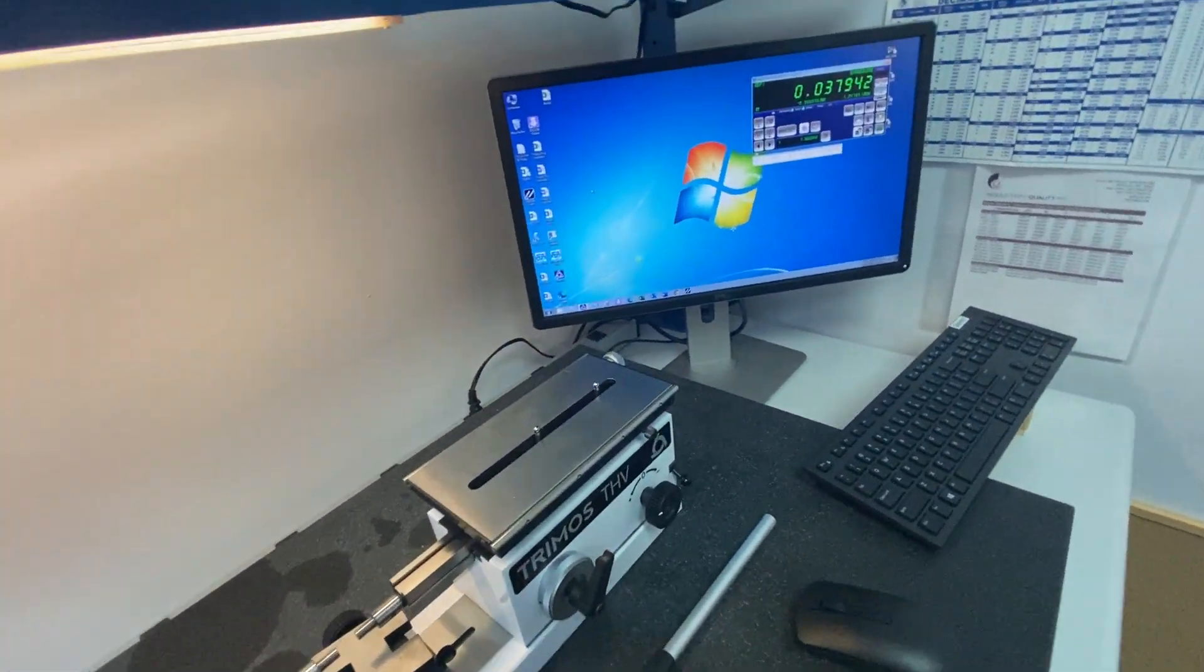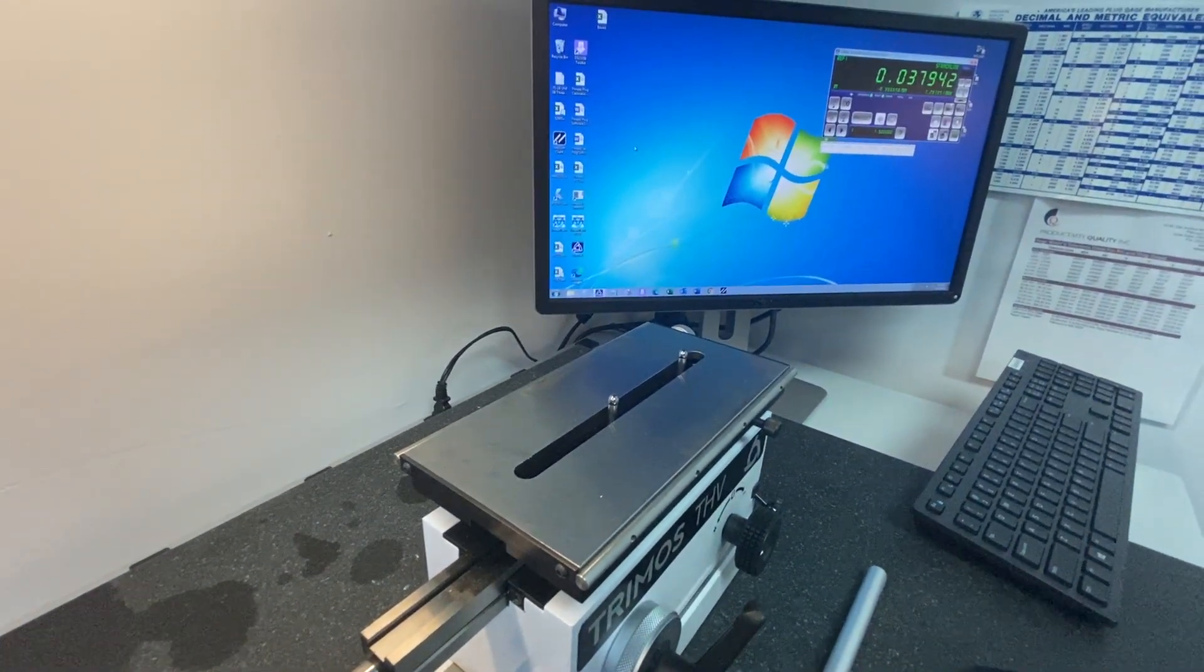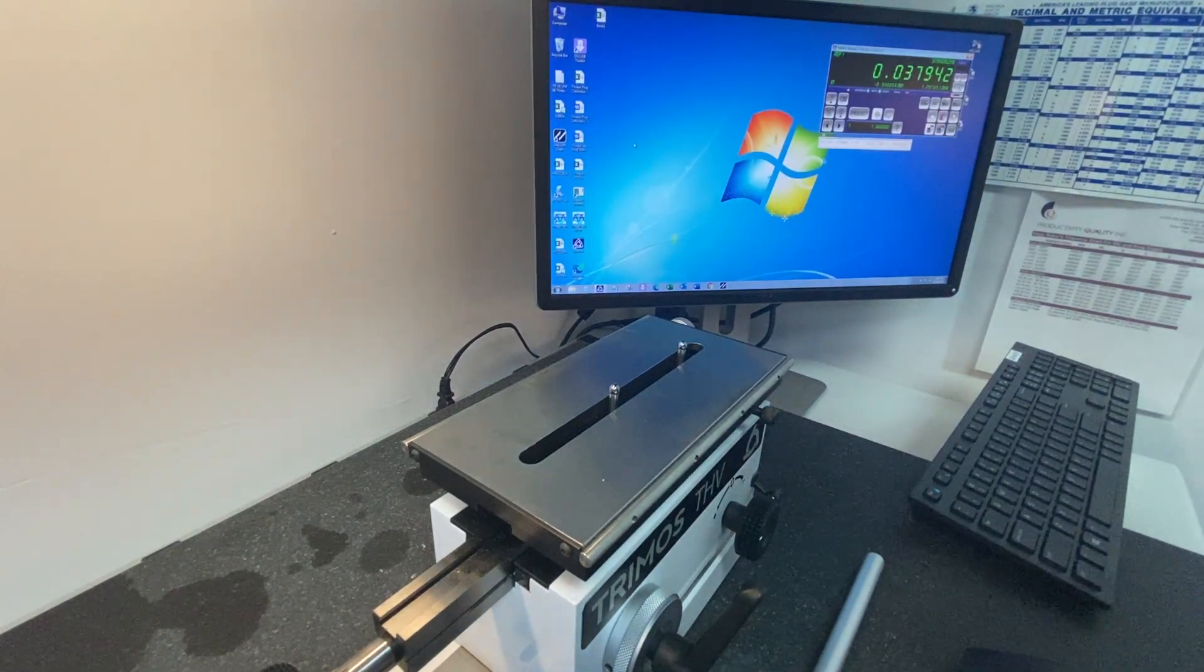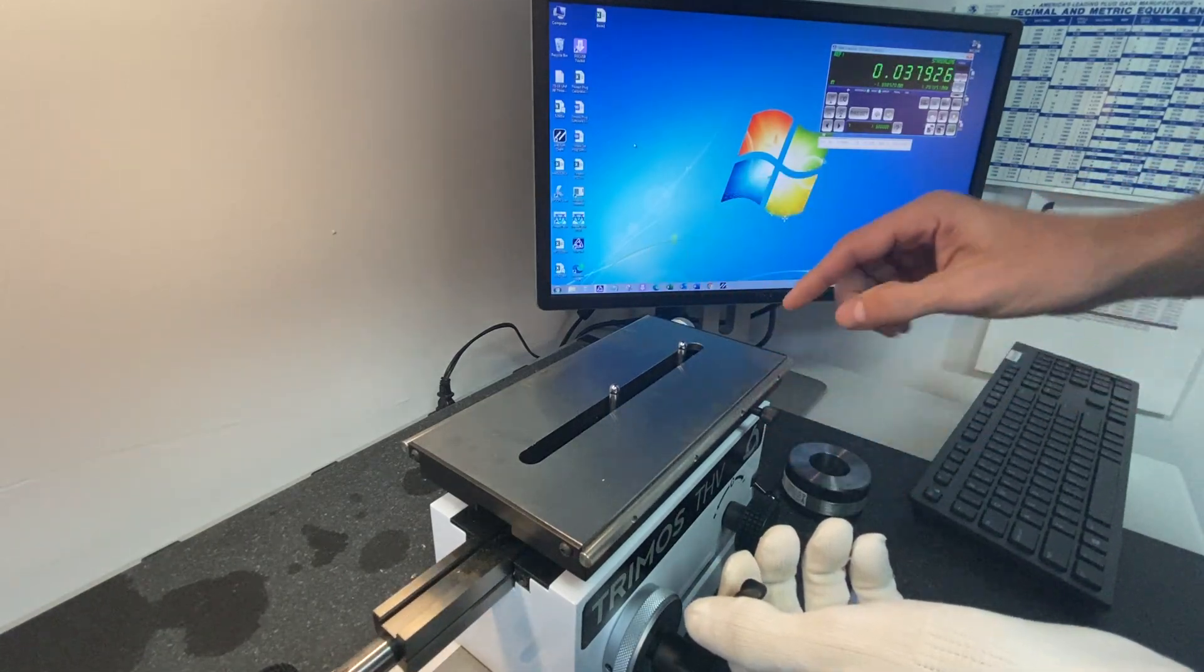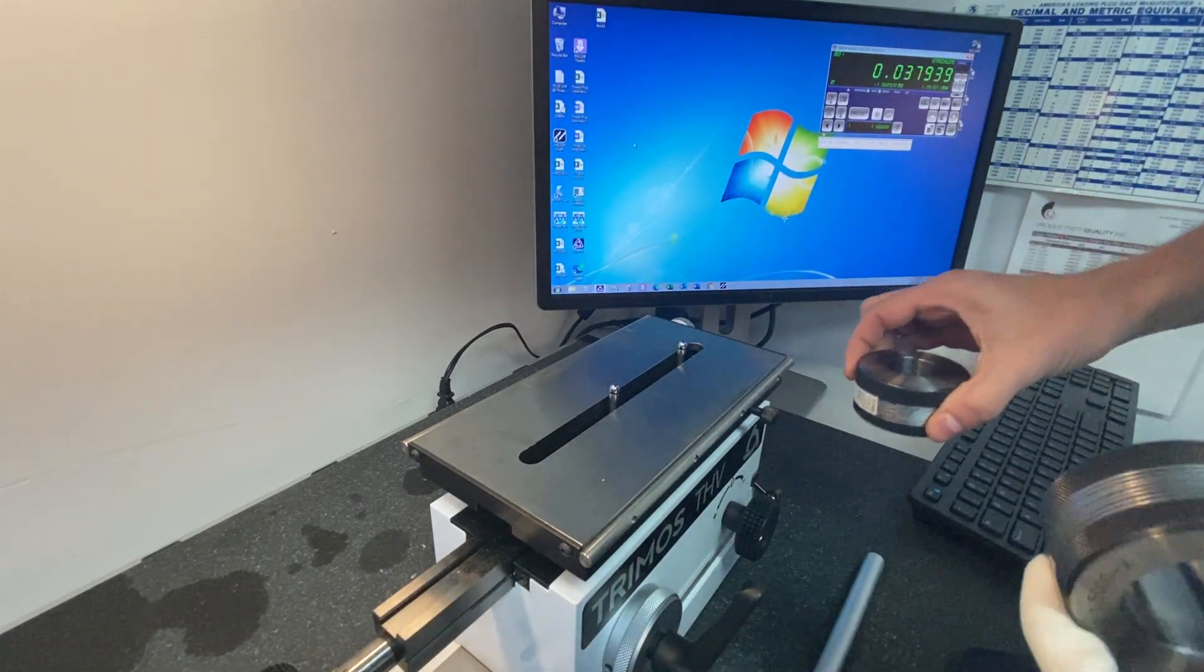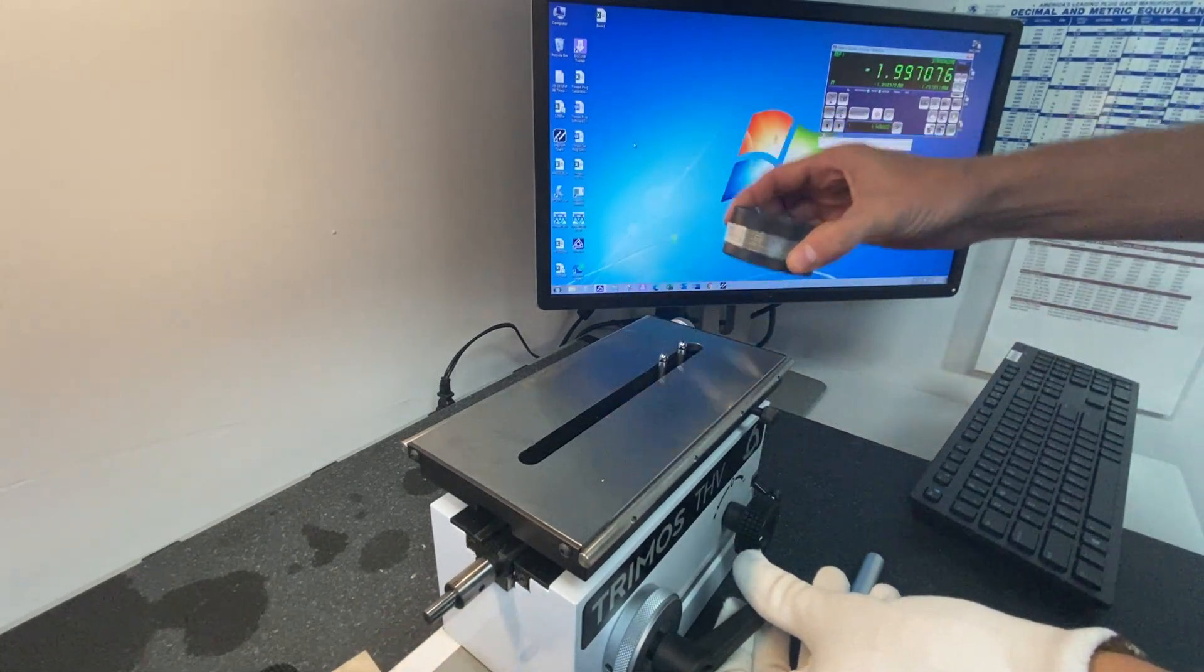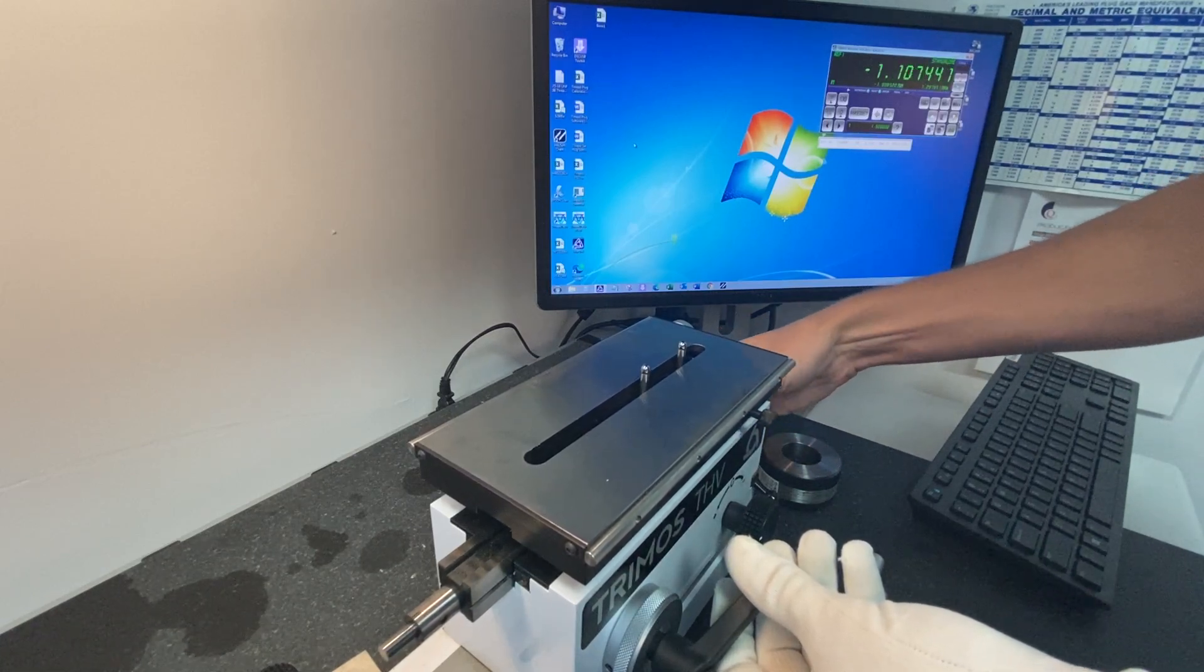We'll be doing this on the THV. I've already set the anvils in their appropriate spots. There was enough travel to measure the 1 inch and the 5 inch rings and we'll make sure the plate is floating. Set my depth.